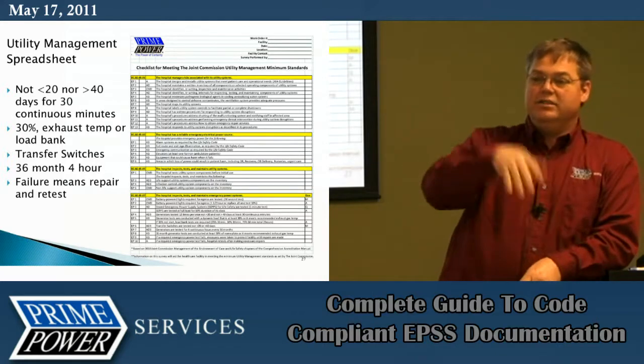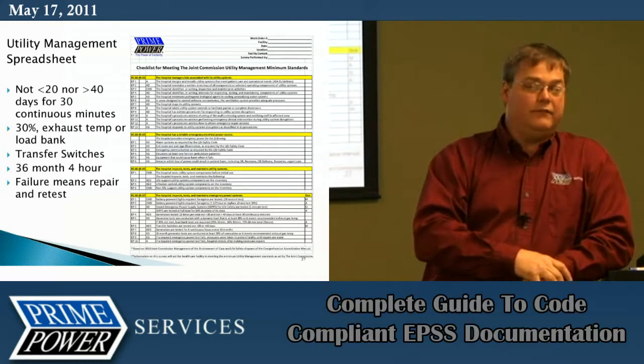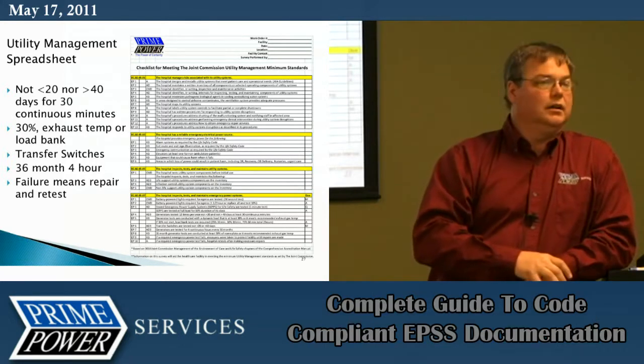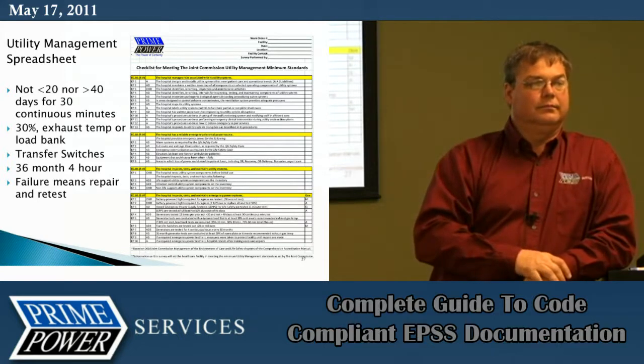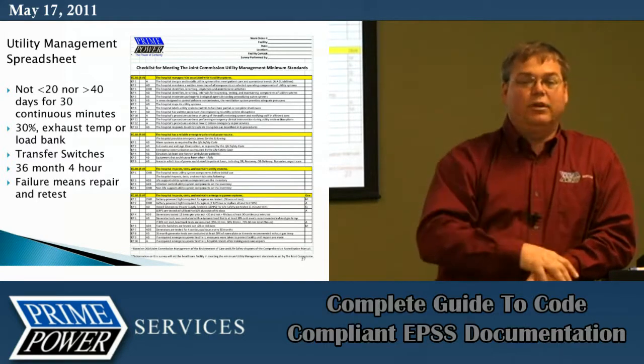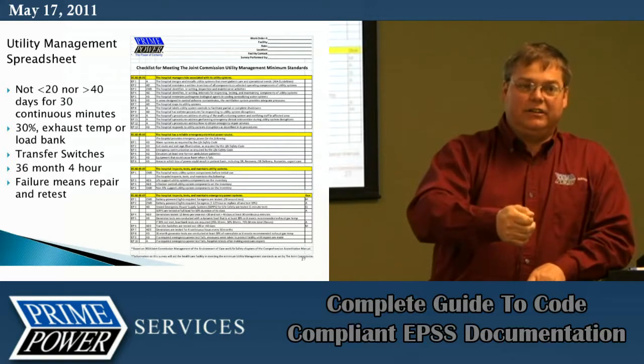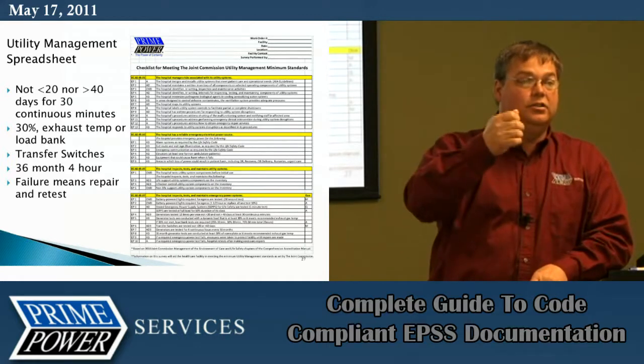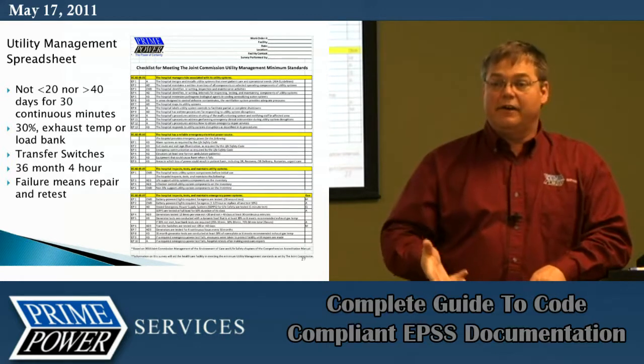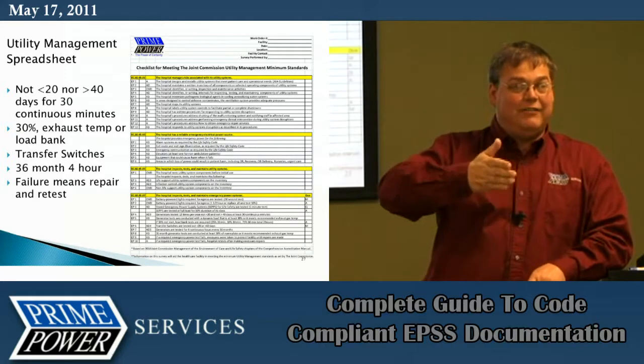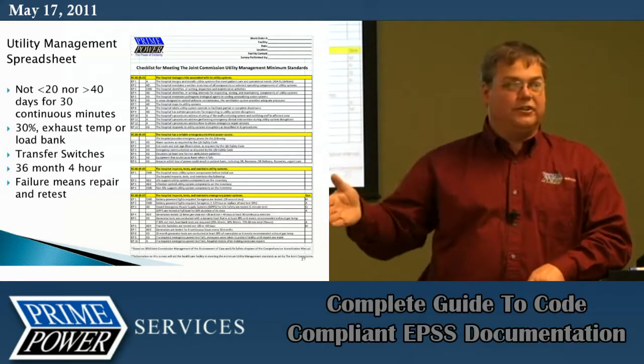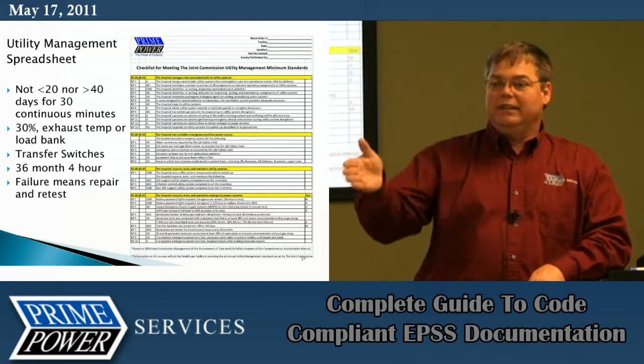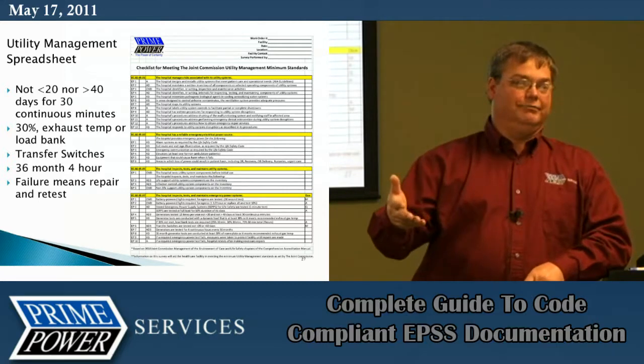You start it with number 1 in January. Do you start it with number 1 in February? No. Why? Because you want each transfer switch to send a signal. Exactly. You want to test the capability of that transfer switch to send that signal to the generator to crank. Once the generator is already cranked, you are testing every time, every month, that they all transfer over. But if you don't rotate that, how do you know that one starts the system?